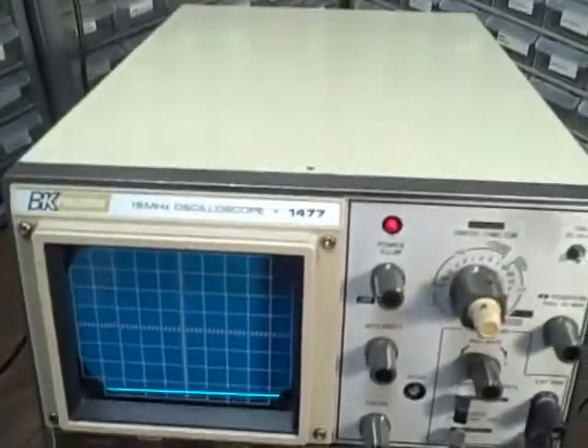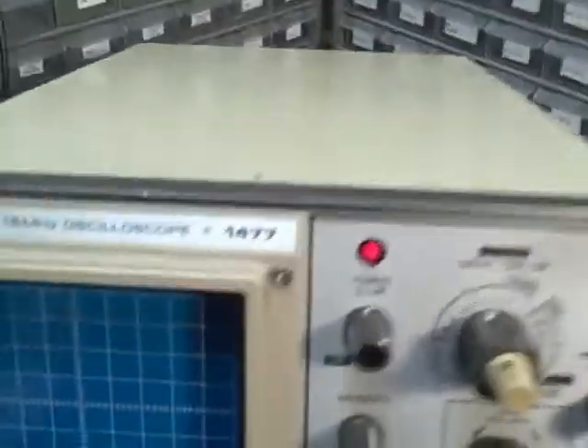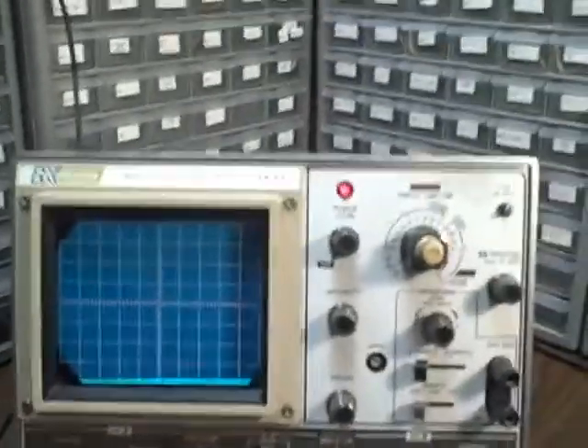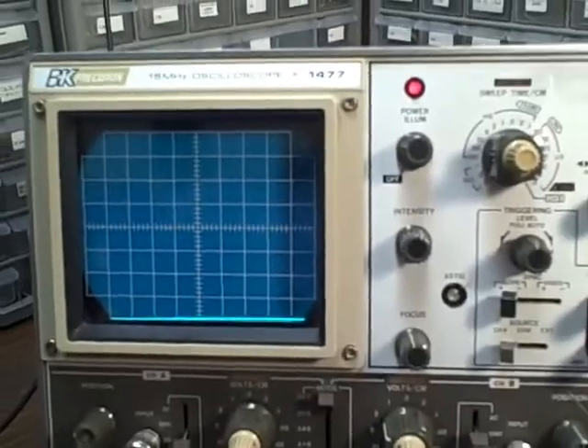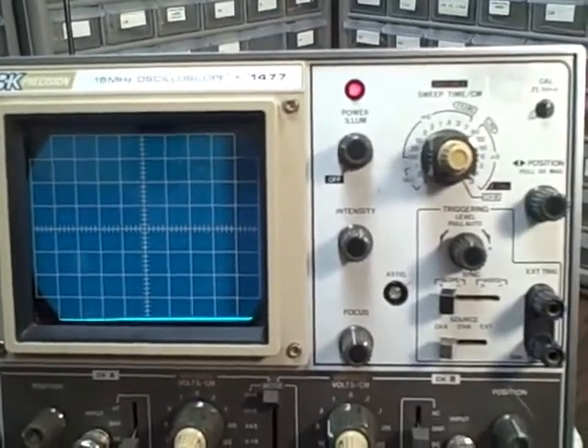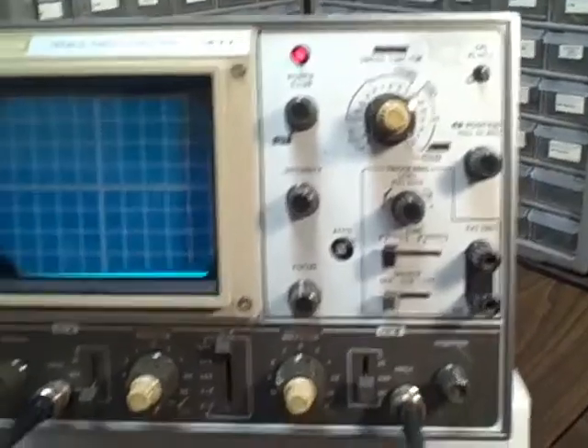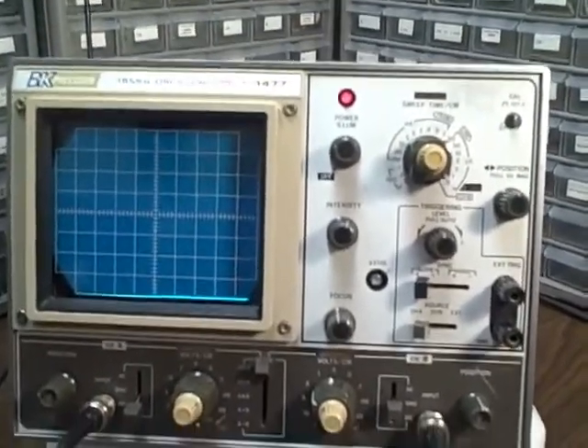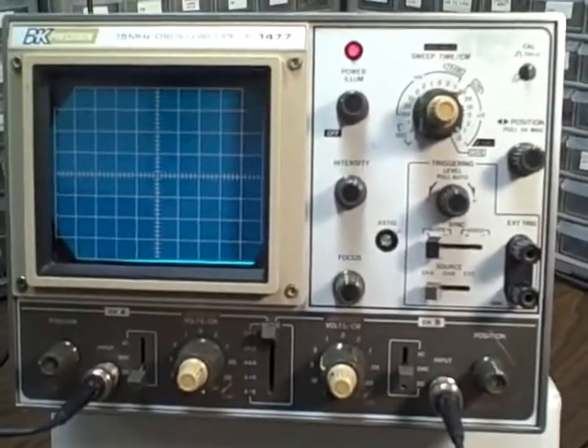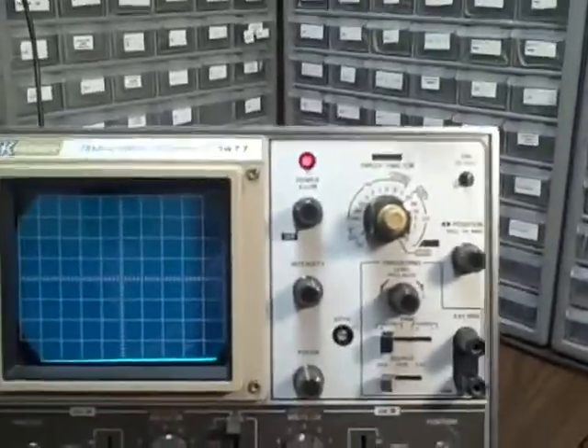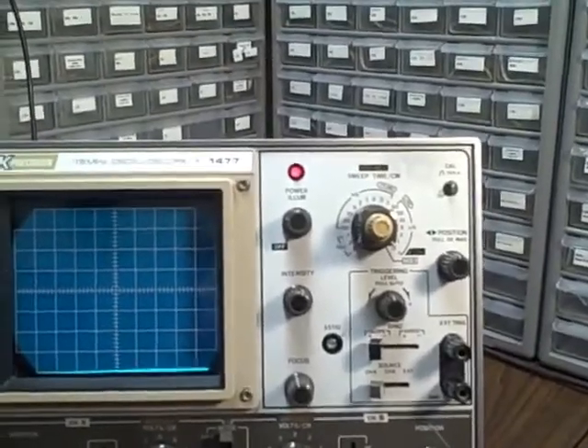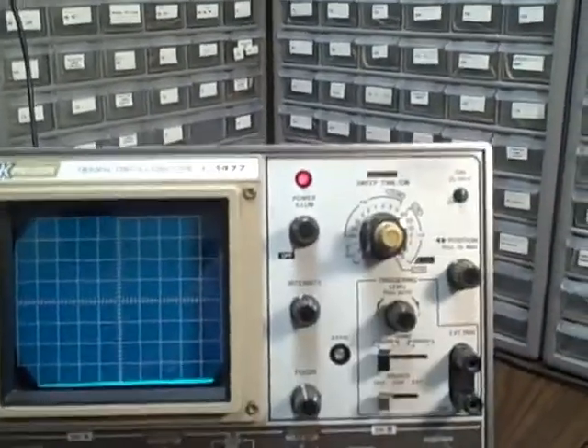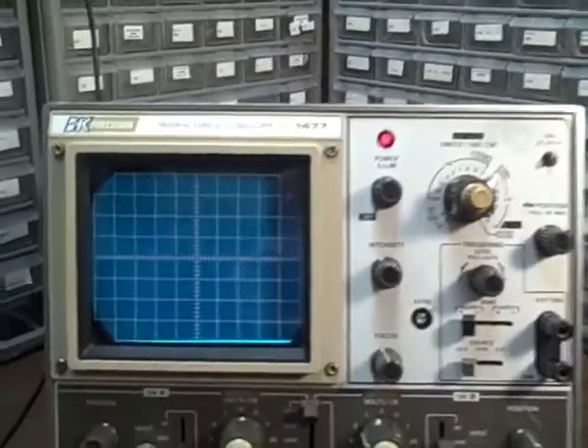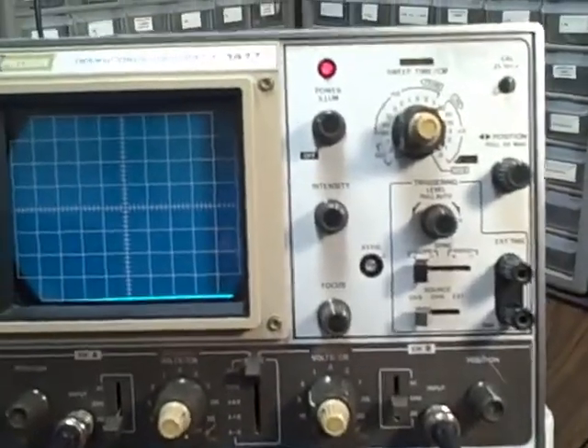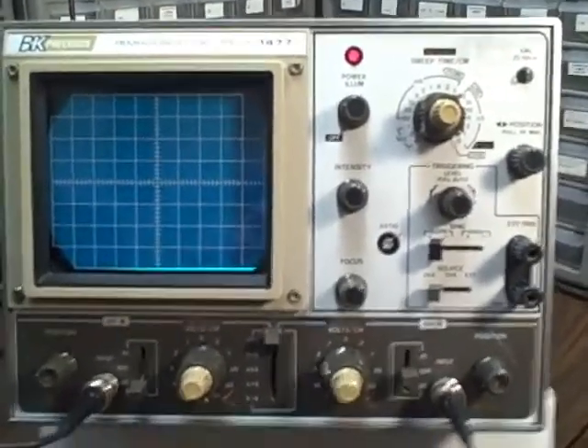Outside of that, though, I was able to completely clean up 27 years worth of tarnish off of the switches and out of the pots, and we've got it. Went through a calibration on it. We have it working very well now. Both, well, in fact, all functions. We have both channels A and B, and magnification working. All of the ranges work, and we're going to take it through some calibration checks to just prove that to you.